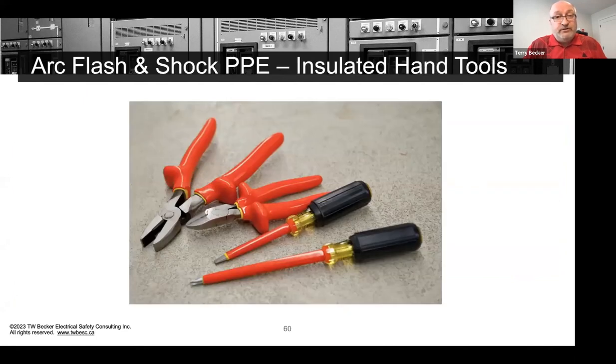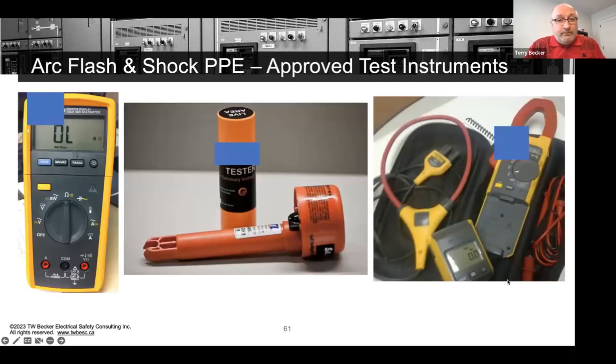If I do have to do energized repair and alteration, one, I would need an energized electrical work permit. And again, I'm just advising you to look to 70E and Z462 for the permit. There are exemptions, but there would be no exemptions for repair and alteration, and you would need insulated hand tools and approved test instruments. So we want an approved test instrument to be used, the right category, the right rating, when the worker has to use these test instruments to go in and do diagnostics and troubleshooting. Readily available, multiple manufacturers out there. The category is an overvoltage transient rating. So for power measurements, we want minimum Cat 3, and that'll be rated for a higher overvoltage transient so the device won't be disrupted if there happens to be a spike while the worker's using it.